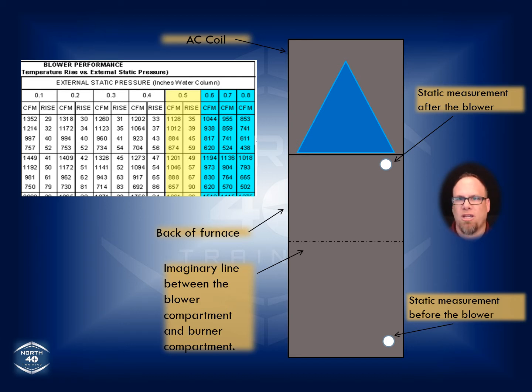This is symbolic, really, to show you that you have to take a measurement before the blower and you have to take a measurement after the blower, and that's got to be in the furnace cavity, so it can't be outside of that. So what is that going to actually do? That's going to show you on your manometer how much resistance is placed on everything after that furnace and before that furnace. How much stress is that blower really under? Because the manufacturers have a specific value that they're looking for. Almost all manufacturers across the board are going to give you a value of 0.5 inches of static that you're shooting for.